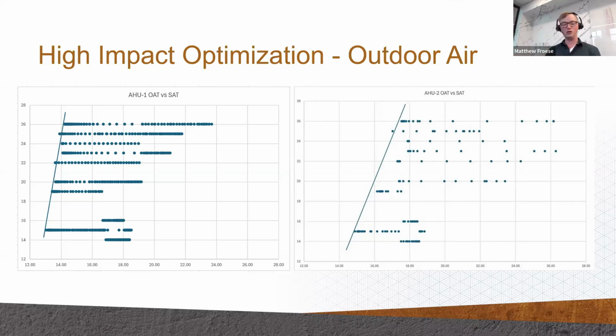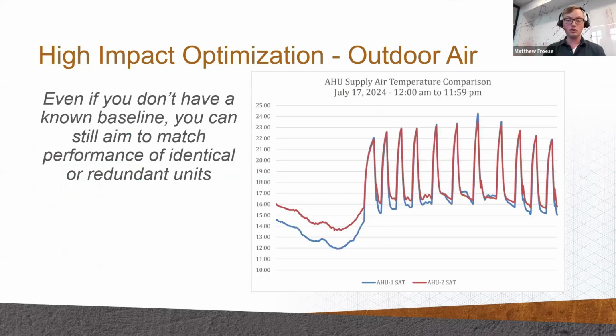Now, in this case, we had to go panning for gold. We had to physically place a sensor, collect the data, and analyze it by hand. But this is the kind of thing that could absolutely be automated to say, hey, you've got a fundamental performance issue. And even though somebody told me that they had checked the damper, they actually hadn't. We went and found that damper was just leaking a substantial amount. And after correction, we managed to get the 2 units, 30-year-old units, performing nearly identically with a simple mechanical fix.